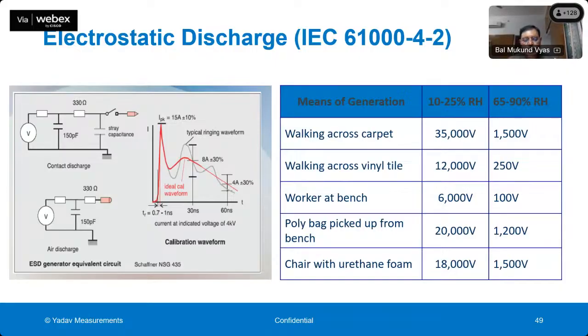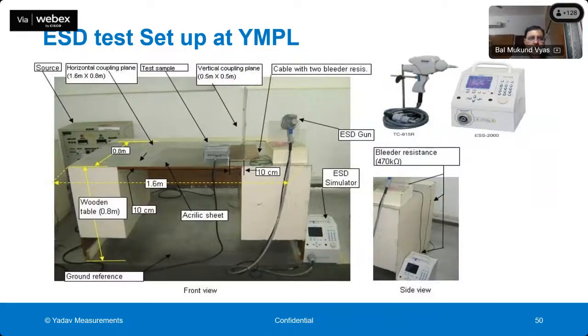If your body is charged with a specified voltage and you go and touch the meter, then all the energy in your body is discharged as a high voltage on the meter, and it can damage the electronics of the meter. So the meter is subjected to such electrostatic discharges. There are specified electrostatic discharge guns available as per the IEC 61000-4-2 standard, and this is the typical setup specified in this standard for testing the meter.